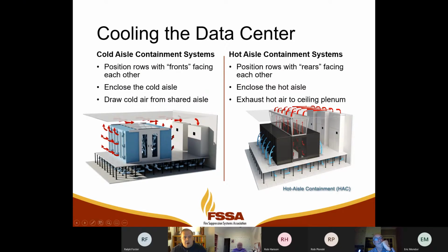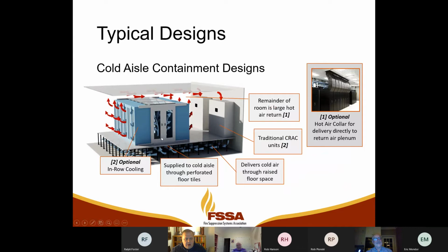So there are cold aisle containment systems and hot aisle containment systems. Let's break those down just a little bit. Cold aisle containment systems, we have our racks arranged to have the cold faces facing each other. We'll put a door on each end and then some sort of roof over top of it, and we'll have the same air distributed under the floor. Generally, a lot of times it'll blow up through perforated tiles in the floor inside the cold aisle, and then out through the hot, into the room. And because of those partitions, there's separation between the cool air and the heated air, and then that heated air goes back to the CRAC units and starts to cycle over again.